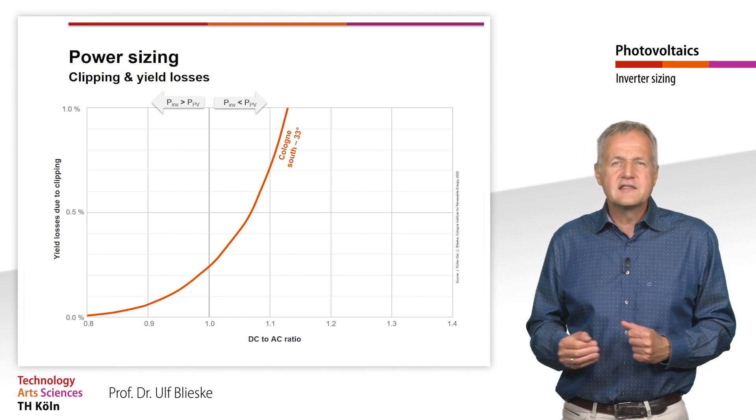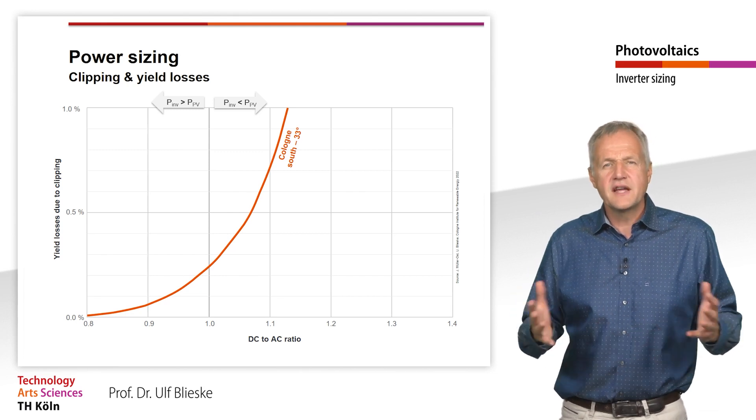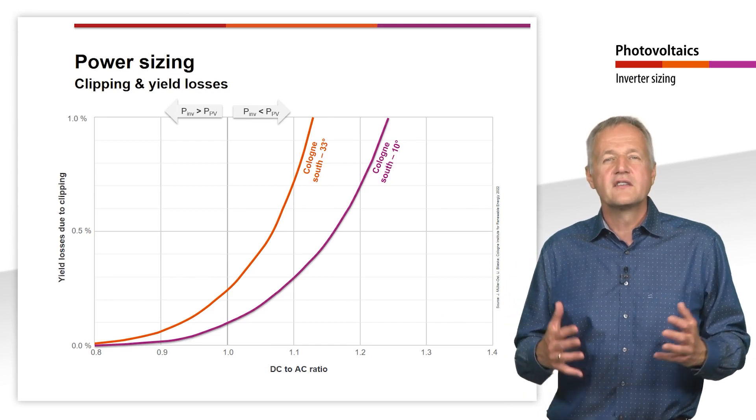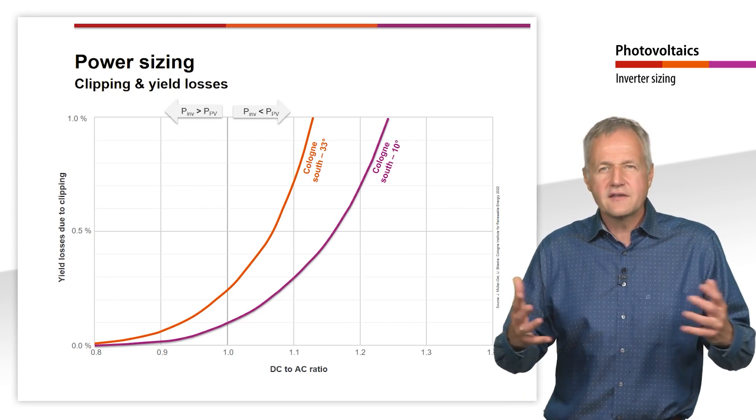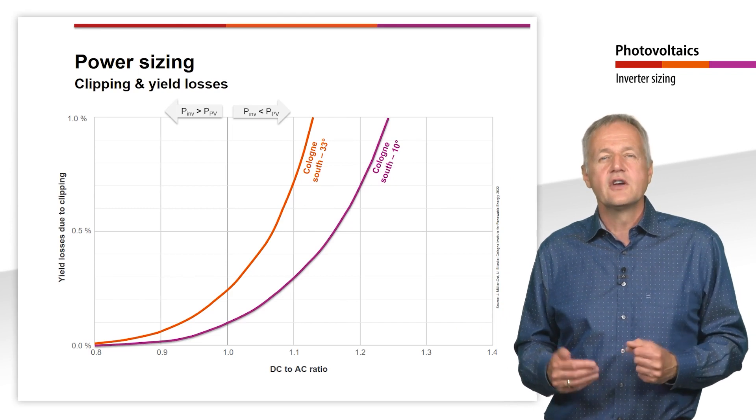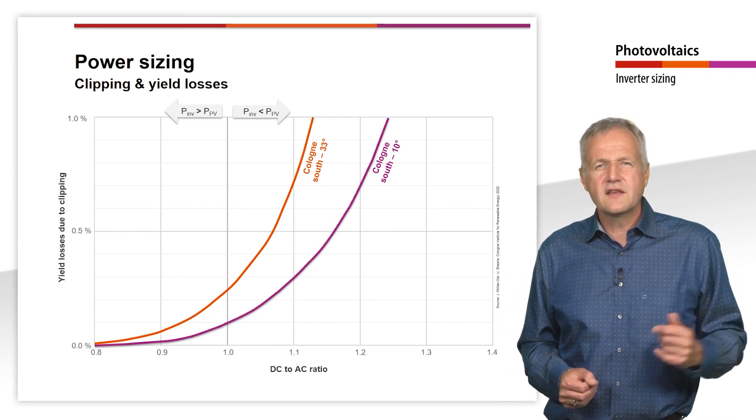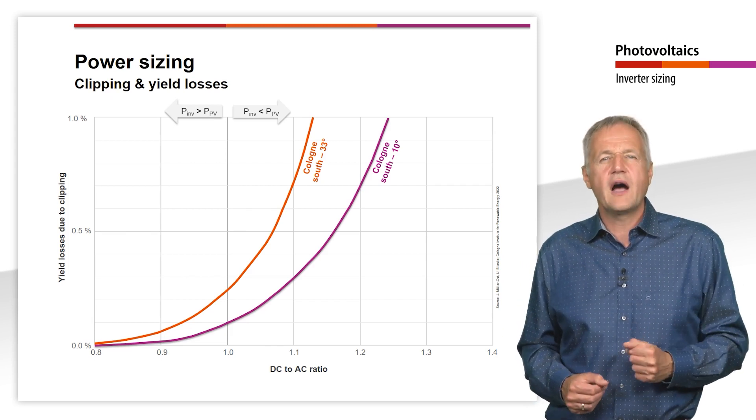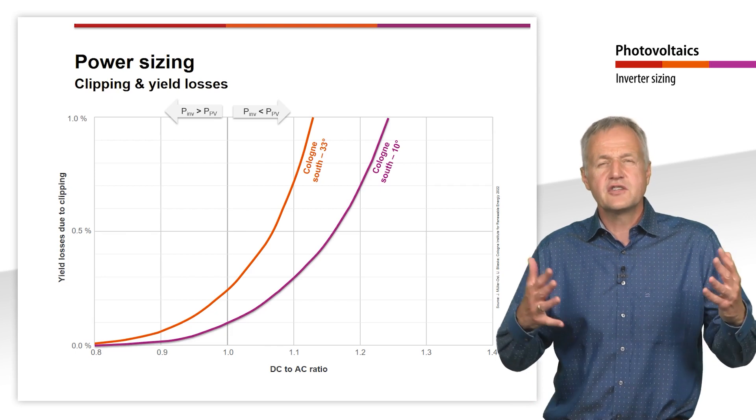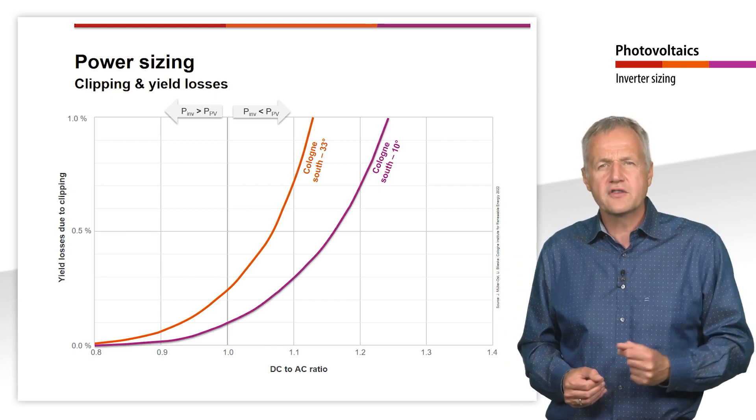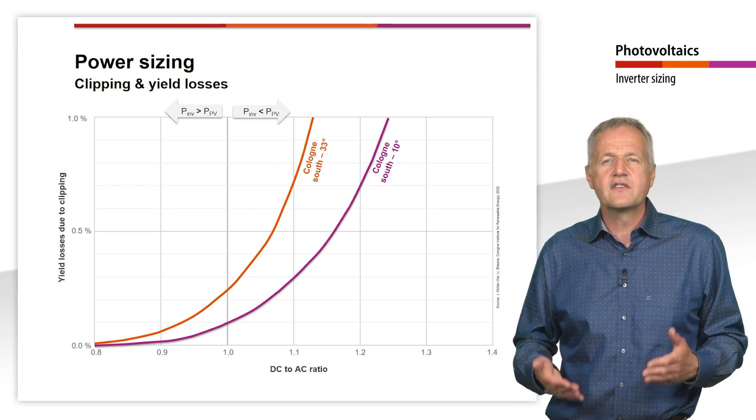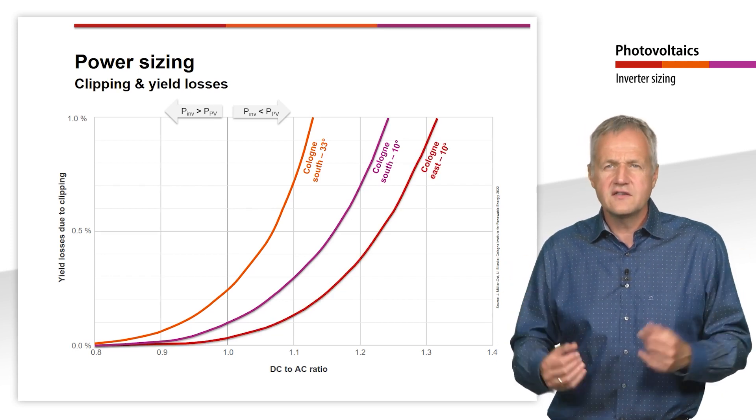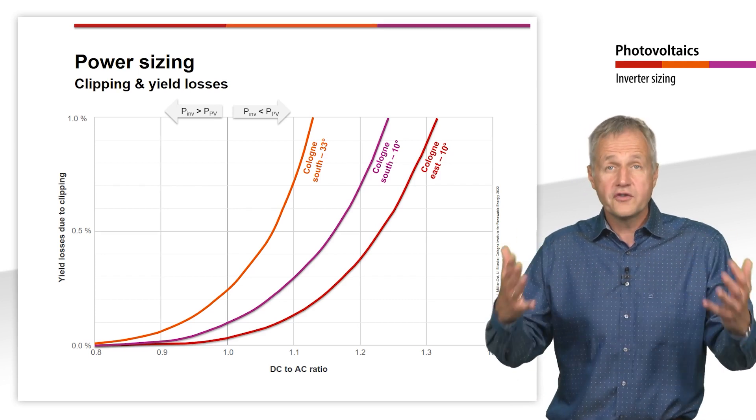For a less deeply inclined plant with 10 degree inclination, however, the inverter can also be sized significantly smaller, since very high irradiance levels occur less frequently due to the lower inclination. In this case, a maximum DC to AC ratio of 1.25 would still be okay. This situation is even more extreme with an east-west oriented plant with 10 degree inclination angle. Here, the DC to AC ratio can even be up to 1.3.